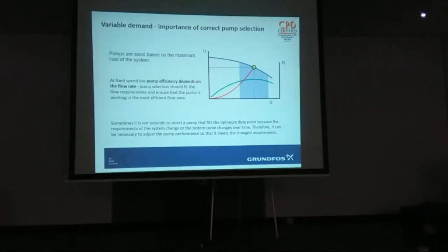So in your specification, you can't put, I want an 80% overall efficient pump. Good luck with that. 70 to 73% is about the best you ever get. And that's what we see in this area here. If you stick an inverter on it, it's less efficient running at 100%. So many people run a pump at 100% speed with an inverter on it. What a waste of time.